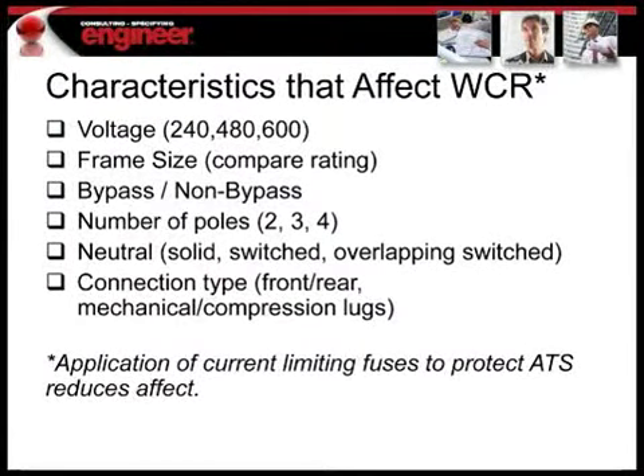So this is a summary of the parameters that you need to consider when you're specifying transfer switches, and these parameters affect the withstand and close-on ratings. The characteristics include the voltage, the frame size of the transfer switch, and whether or not the switch is a bypass or non-bypass isolation type switch. How many poles do you need for your switch? Typically a switch is 3 or 4 pole. Whether or not the switch uses solid switch or overlapping neutral contacts also influences the ratings. And then the type of connection to the switch, whether it's front-mounted, front and rear accessible, or top connection, affects the withstand and close-on rating.